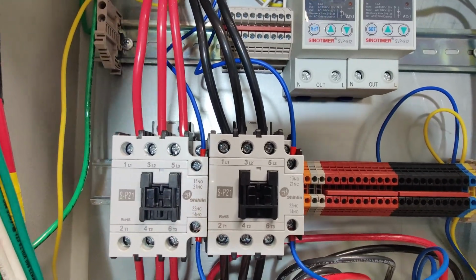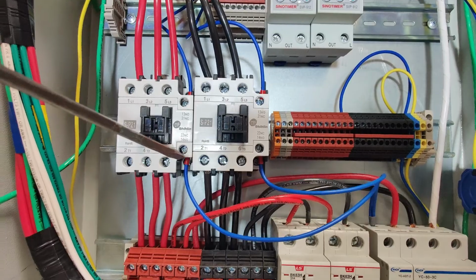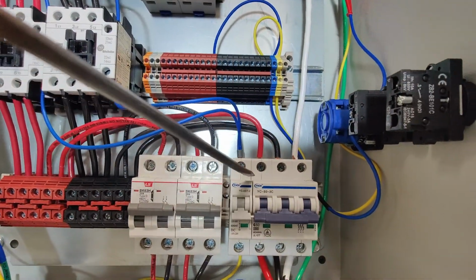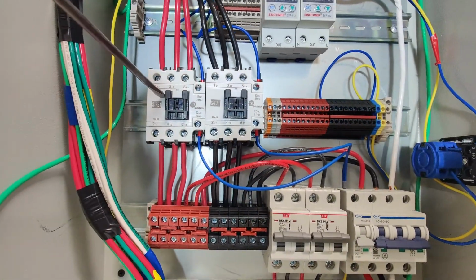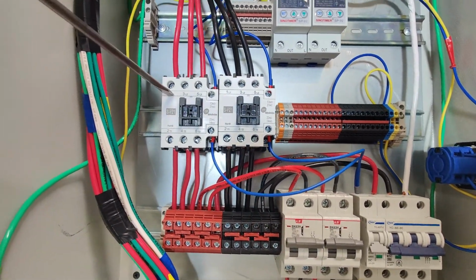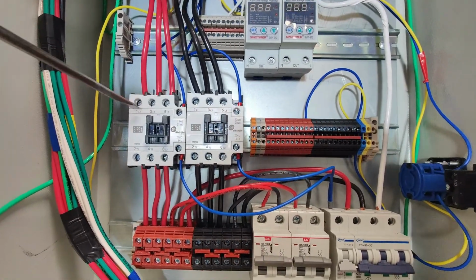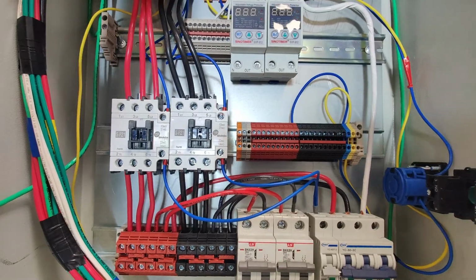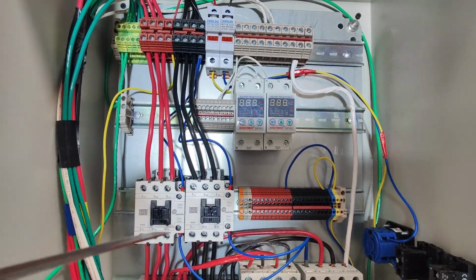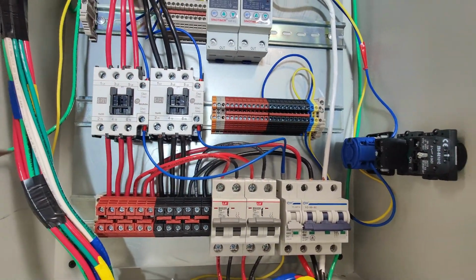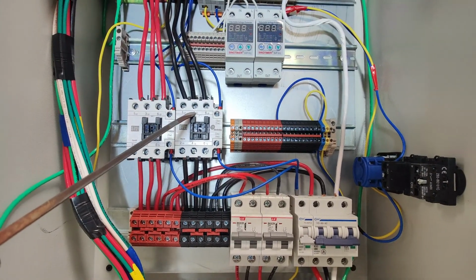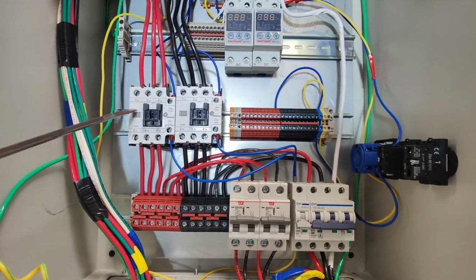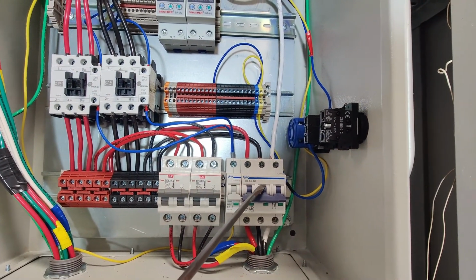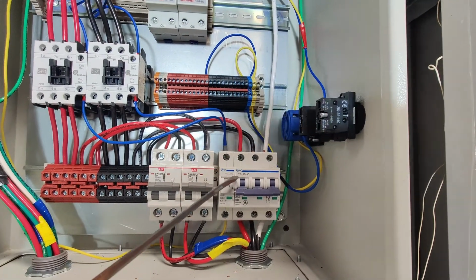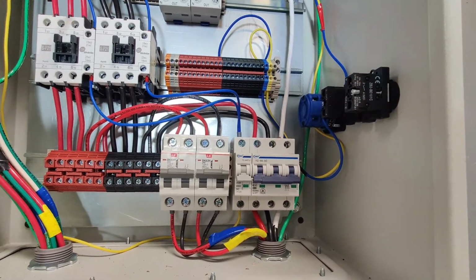So both wires come down into the contactors, and then they both come out of the NC side over to the other side of the shunt trip. And what this does is, if either contactor, either this one or this one, fails and is closed while operating in normal conditions, it's going to allow that other hot leg from up here to pass through and create a connection on our shunt trip, and that's going to trip the breaker. So this means that we can't have a condition where one hot leg is operational and the other hot leg is not operational and still have this main breaker open, or I'm sorry, closed. We can't close this breaker without both of these contactors being active.